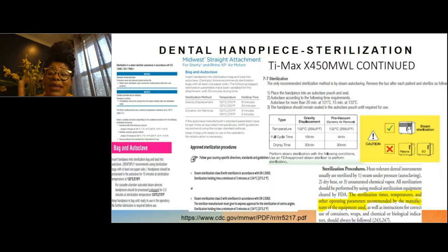These are excerpts from many different handpiece IFUs with all sorts of different sterilization times. I want to say that it can't just be put inside that autoclave and hit a button. You can see there are times, depending on what kind of sterilizer you're using, there are times for a gravity displacement. There are times for a pre-vacuum sterilizer. It's important to read the IFU so you can know what time to set your autoclave to, so that your handpiece is sterilized according to what the manufacturer's recommendations are.